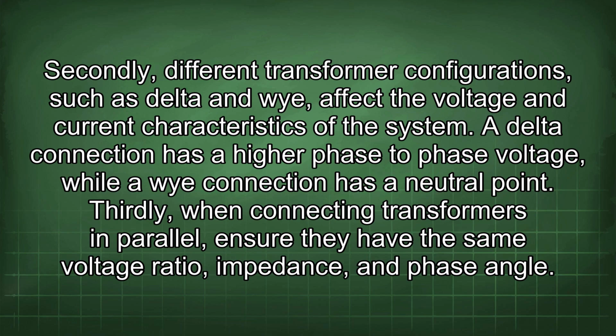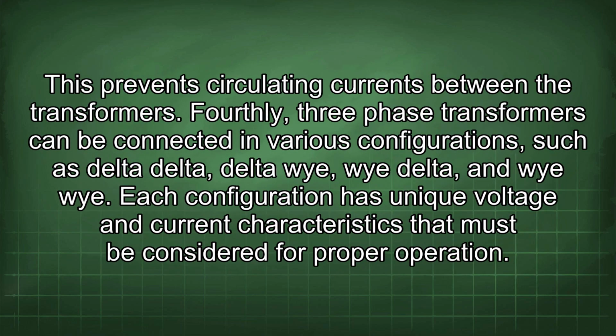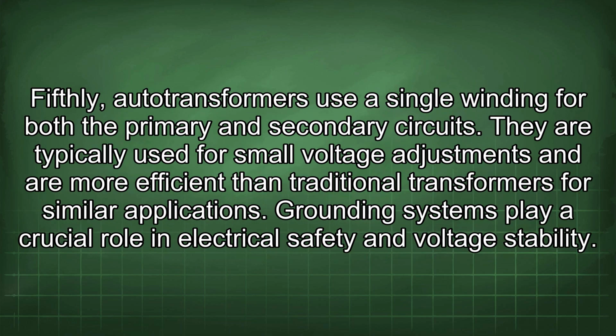Thirdly, when connecting transformers in parallel, ensure they have the same voltage ratio, impedance, and phase angle. This prevents circulating currents between the transformers. Fourthly, three-phase transformers can be connected in various configurations, such as delta-delta, delta-Y, Y-delta, and Y-Y. Each configuration has unique voltage and current characteristics that must be considered for proper operation. Fifthly, auto transformers use a single winding for both the primary and secondary circuits. They are typically used for small voltage adjustments and are more efficient than traditional transformers for similar applications.